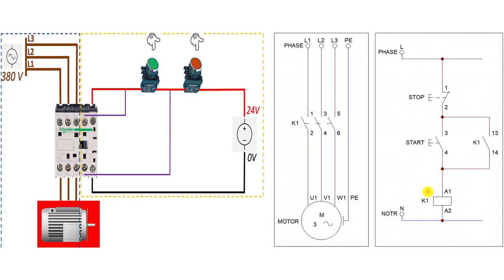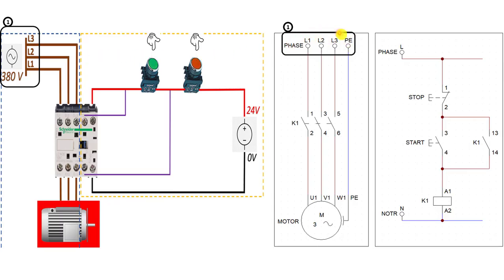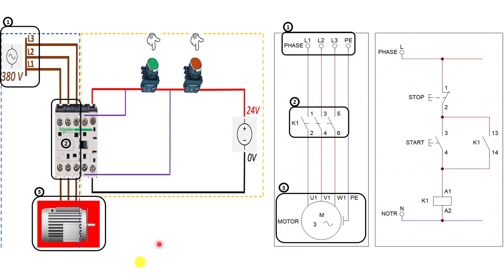This physical connection is shown in the electrical circuit diagram. The left side shows the power circuit and the right side shows the control circuit. Let's match them one by one. The 380-volt three-phase mains voltage is shown in the diagram as L1, L2, L3, and ground. The three main contacts in the circuit diagram show: main input contacts are 1, 3, 5 and output contacts are 2, 4, 6. The load, which is the motor, is also represented symbolically.